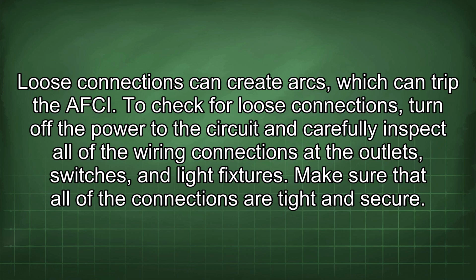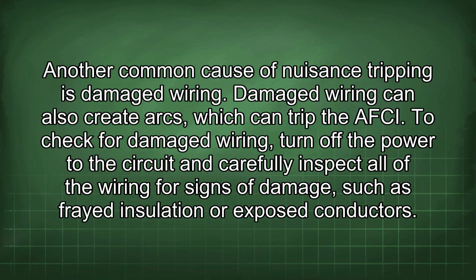To check for loose connections, turn off the power to the circuit and carefully inspect all of the wiring connections at the outlets, switches, and light fixtures. Make sure that all of the connections are tight and secure. Another common cause of nuisance tripping is damaged wiring. Damaged wiring can also create arcs, which can trip the AFCI.